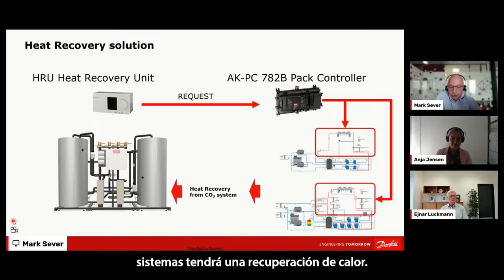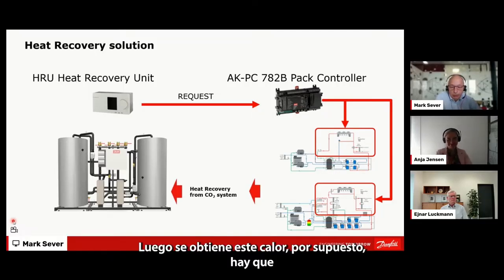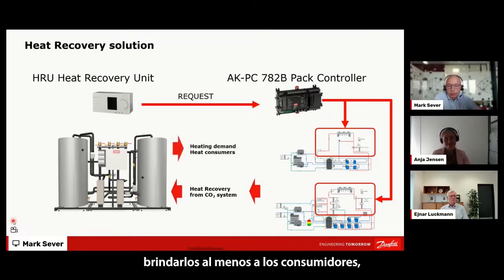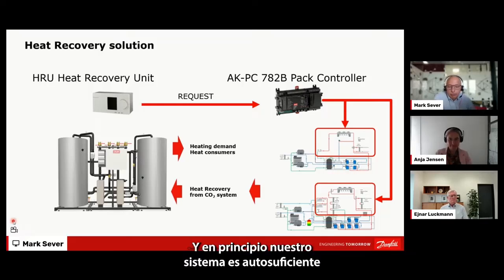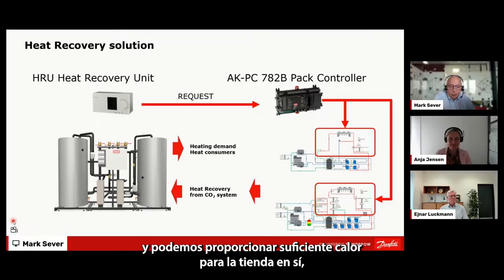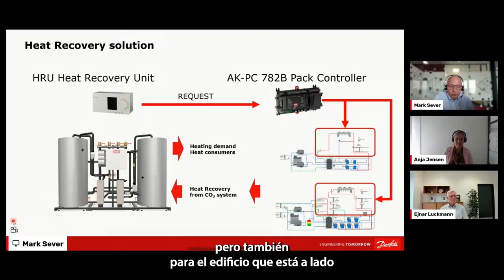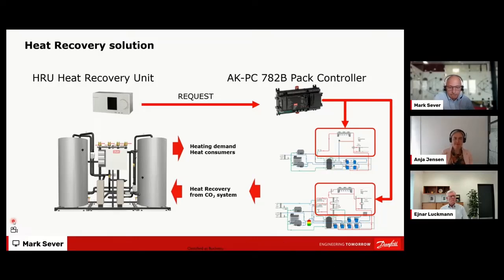And then from one of those systems, you will have heat recovered to your system. When you get this heat, you have to provide it to the consumers, either air handling unit, fan coils, or radiators. In principle, our system is self-sufficient, and we are able to provide enough heat for the store itself, but also for the additional building next by.